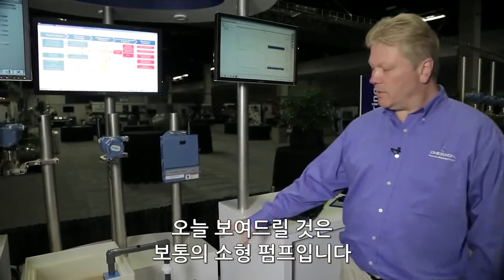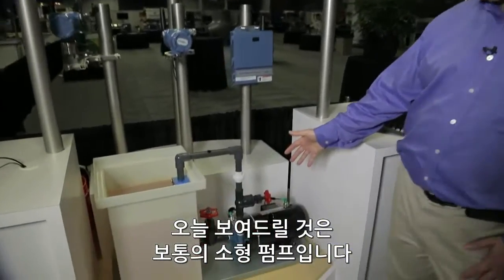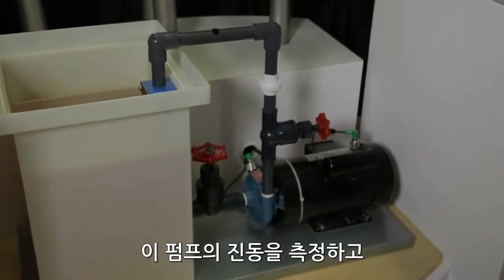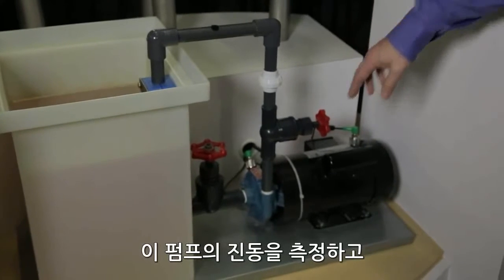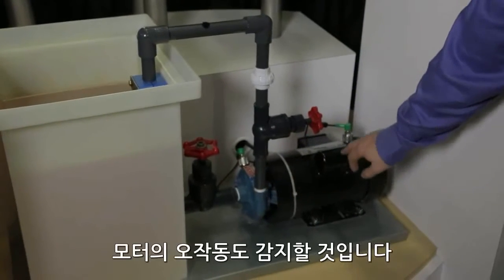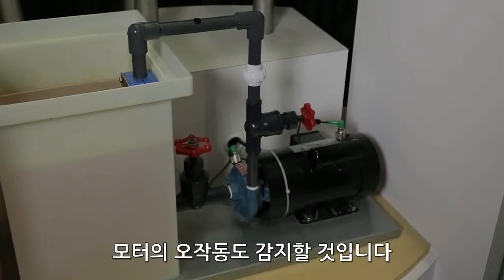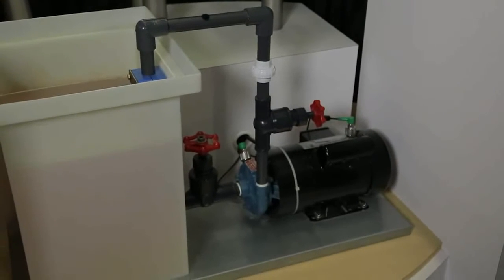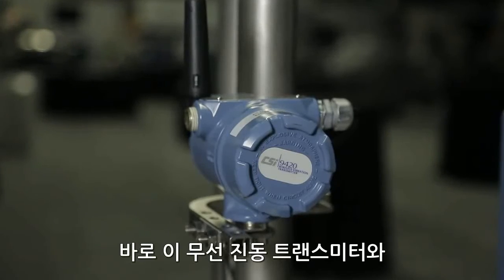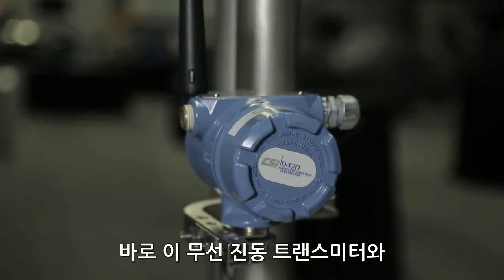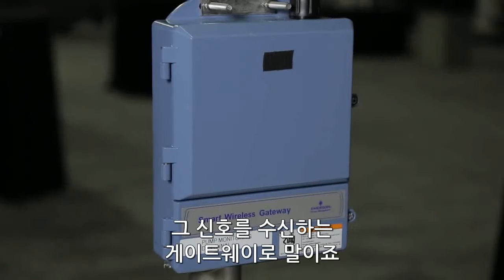So today I have a regular little pump in which I'm going to be measuring the vibration on the pump and actually on the motor, because motors fail also. And I have a wireless vibration transmitter and a gateway to get that signal.